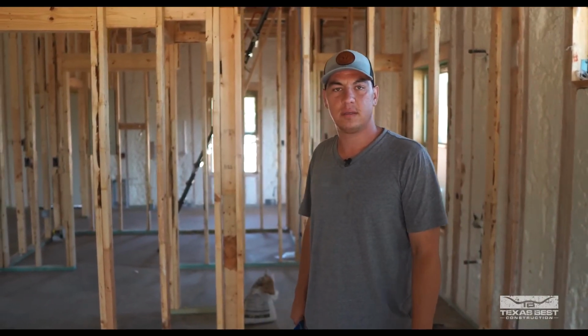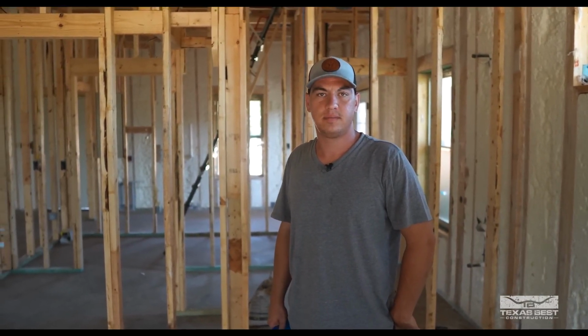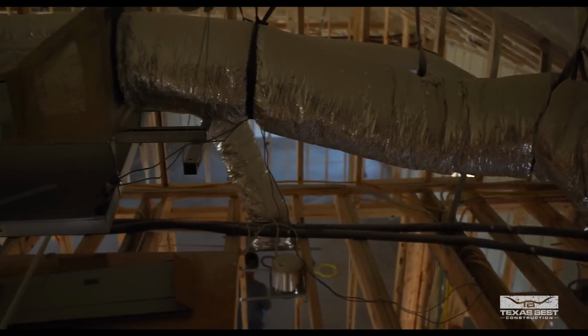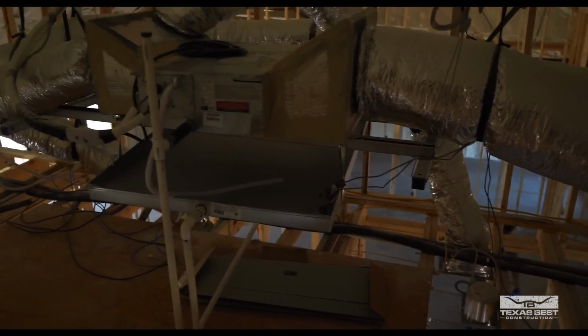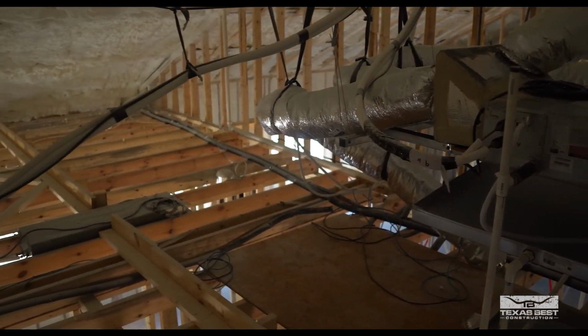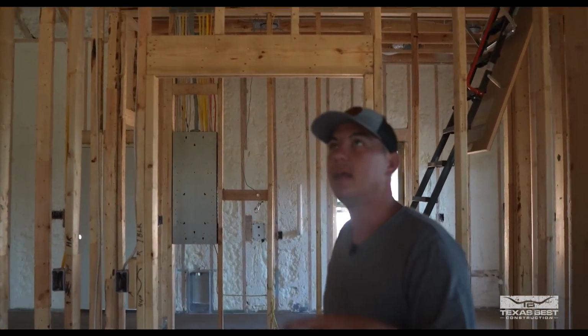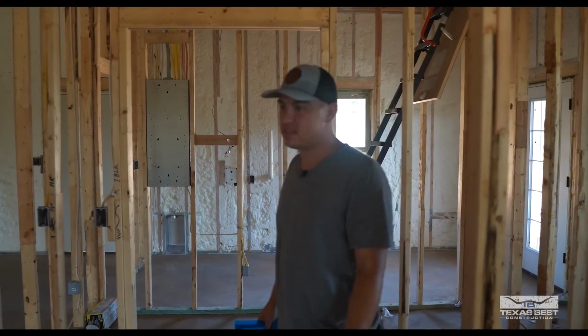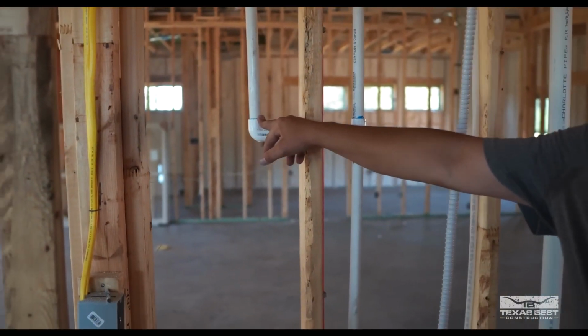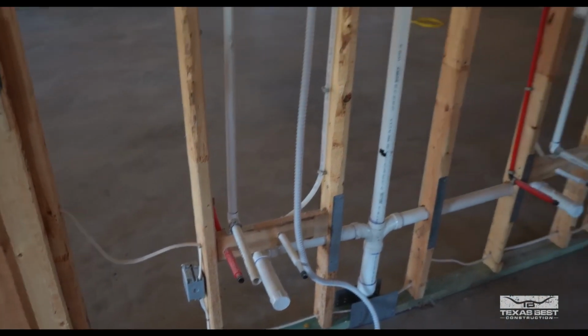So as we are looking into these other rooms, now you got a little more of a conventional system going for the bathroom over here, I see. Right. So we have a 9,000 BTU. It's kind of hard to see it here because we've got the decking, but it's a slim duct. 9,000 BTU would be about 3/4 of a ton. And this is controlling your master bedroom, master closet, and laundry room space with, again, its own individual zone and thermostat. This one as well, we are adding the Wi-Fi control. It's not a standard option, but with Cooper&Hunter, they offer the Wi-Fi. So this is coming off of your cassette, and then this is your slim duct. And that'll tie in under the sink, just like any conventional air conditioner.